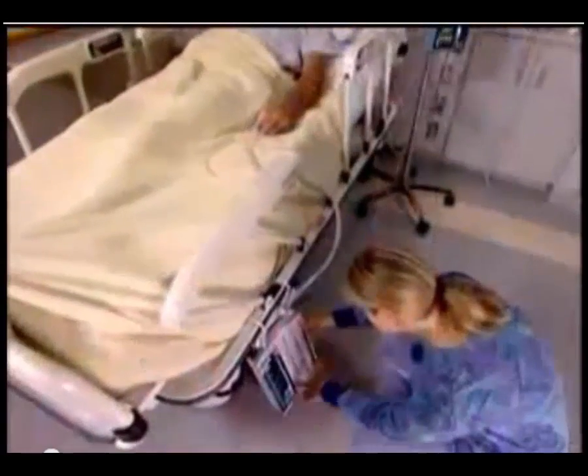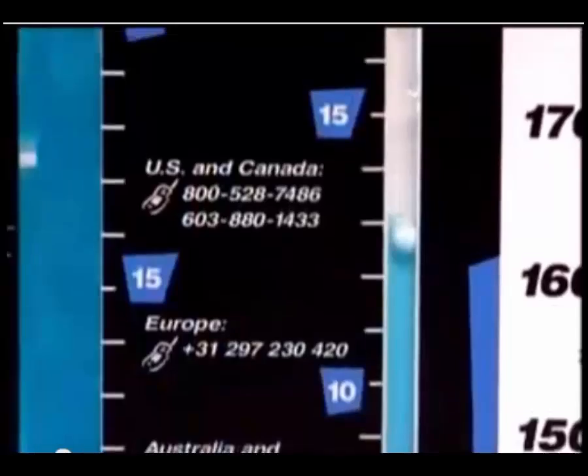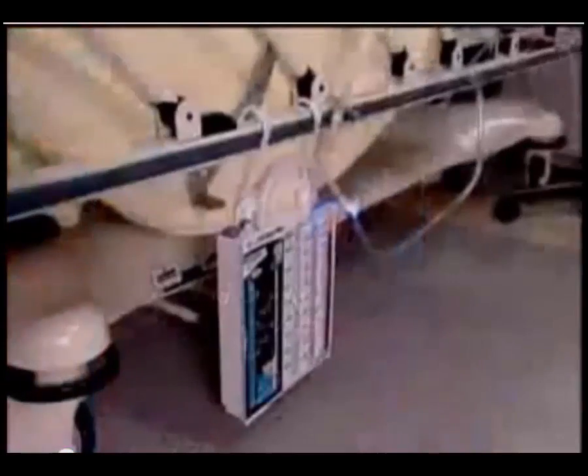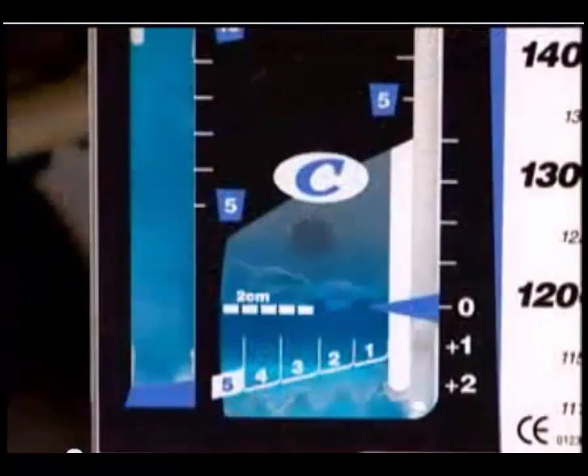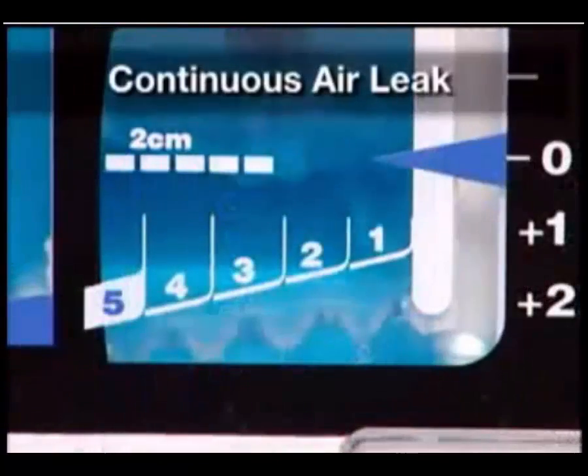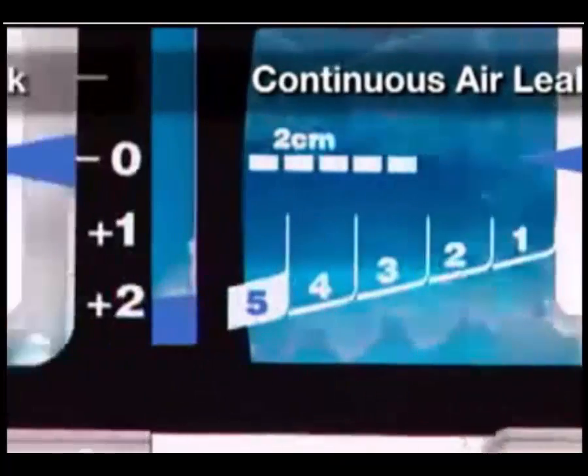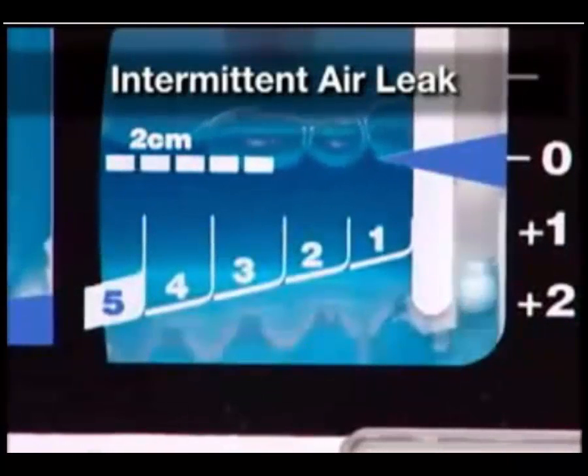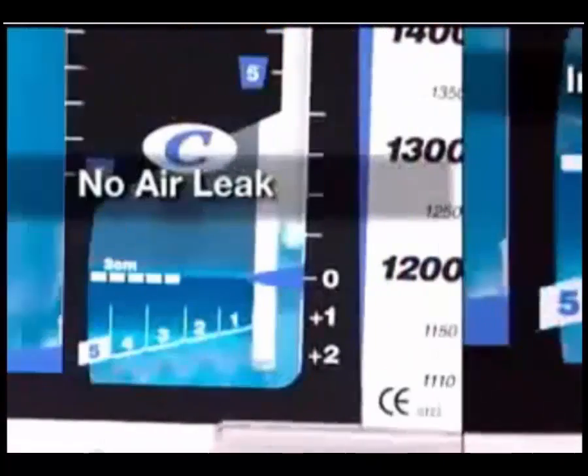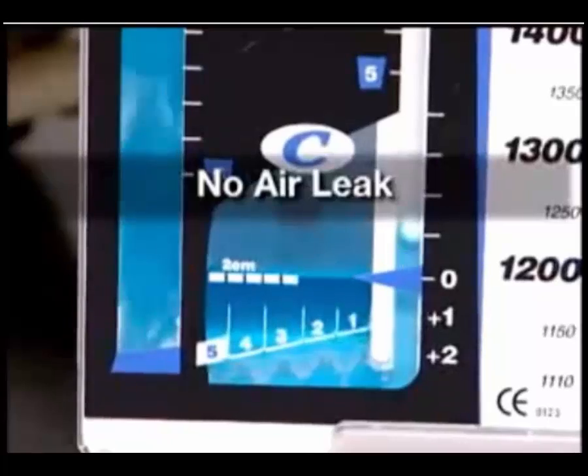It's also a very useful diagnostic tool, as it can show even the smallest trends of an air leak, as well as changes in intrathoracic pressure. Assessing patient air leaks is easy with Atrium's Blue Tint Water and Air Leak Monitor. Continuous bubbling observed in the water seal will confirm a persistent air leak in either the patient's thoracic cavity or possible tube connections. Intermittent bubbling with gentle float ball oscillation will confirm the presence of an intermittent air leak.